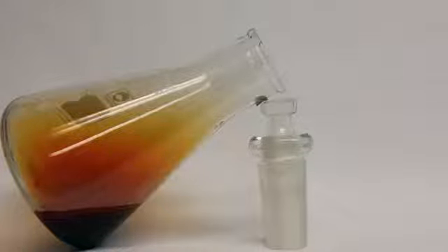HB2 is the safest mineral acid to use around sodium hypochlorite bleach. Any other mineral acid, hydrochloric, sulfuric, nitric or phosphoric, would have yielded very volatile chlorine gas. This would rapidly dissipate into the atmosphere as a green gas, causing discomfort and even injury to employees in the immediate vicinity.